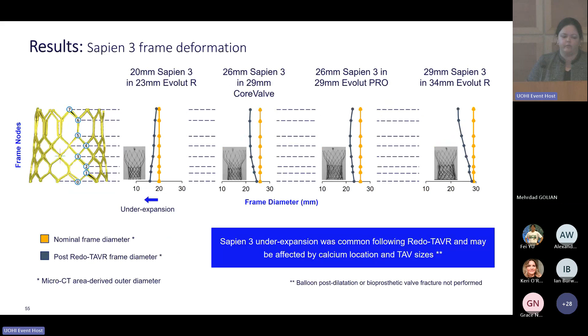But maybe one of the most important findings from this study is that when we used failed valves instead of pristine valves, what you can see in this video and in this photo as well is that calcium from that failed valve is actually extruding through the frame of the second valve that's been implanted. And every time that valve is opening and closing, it is hitting that calcium. So your brand new SAPIEN 3 leaflet that's supposed to last 8 to 10 years is hitting a piece of calcium every single time, and that calcium is quite sharp, and it's doing it in multiple areas throughout the valve, and something that is quite problematic.